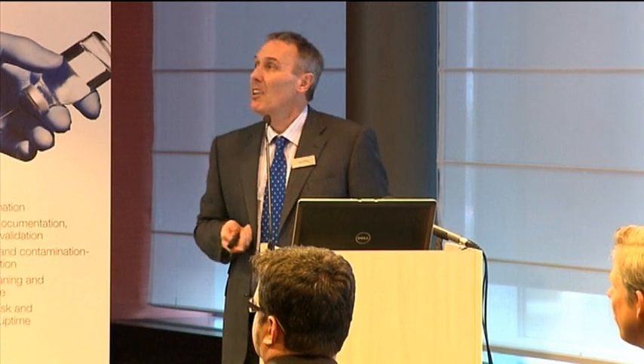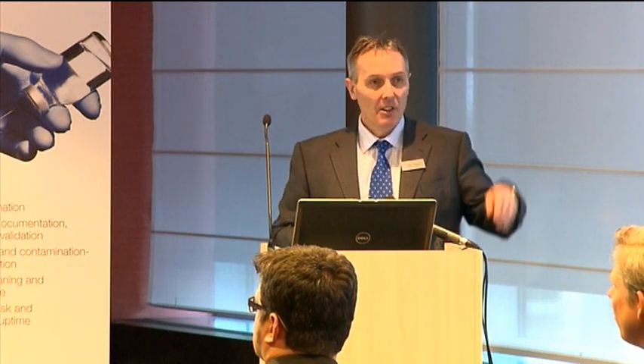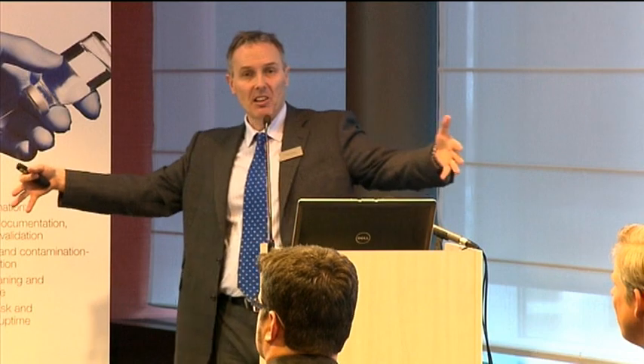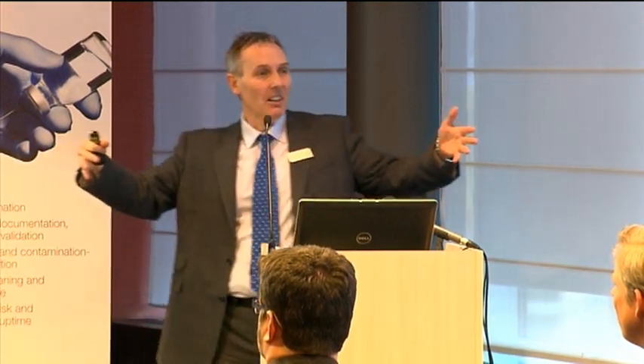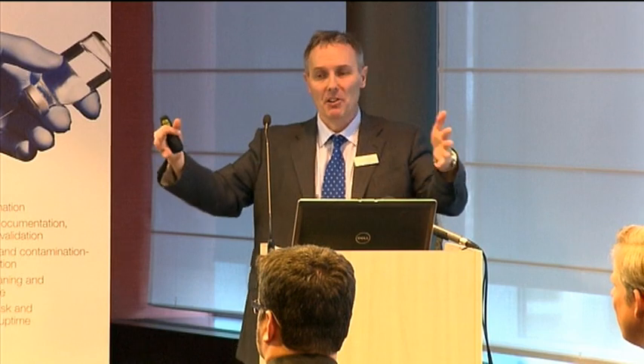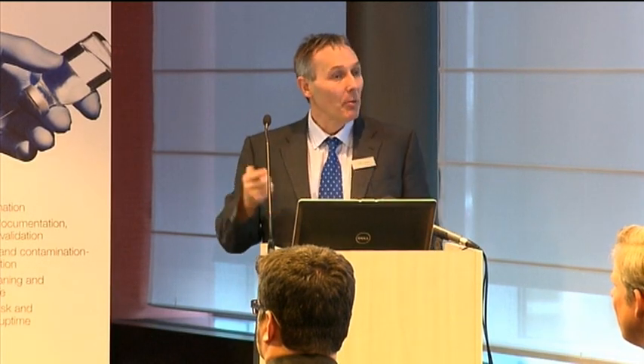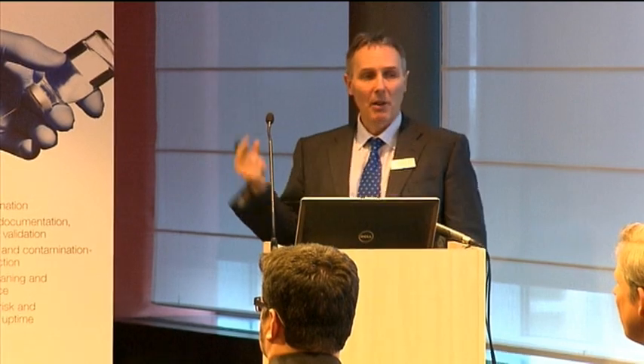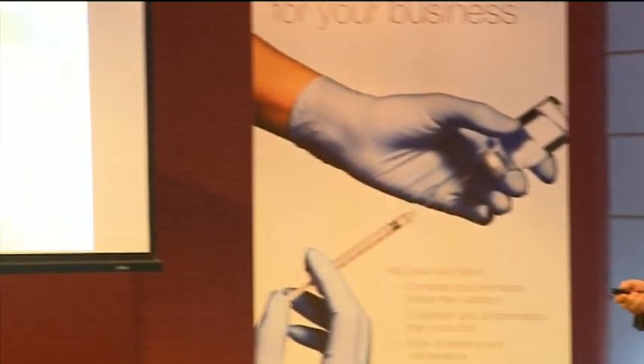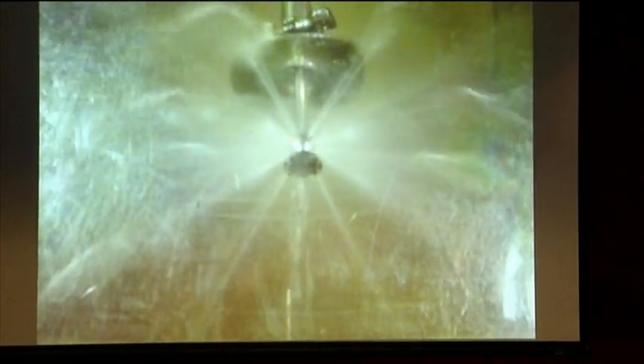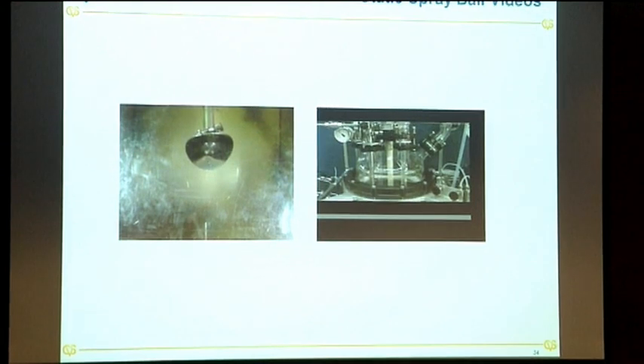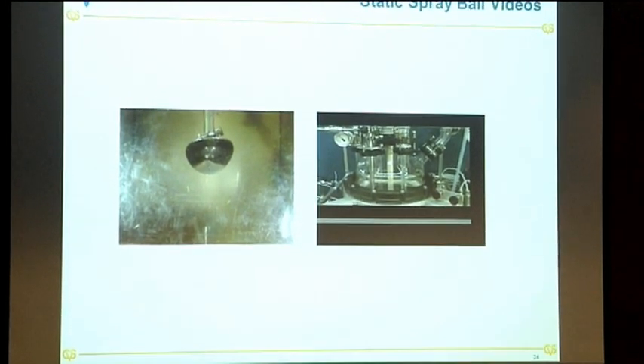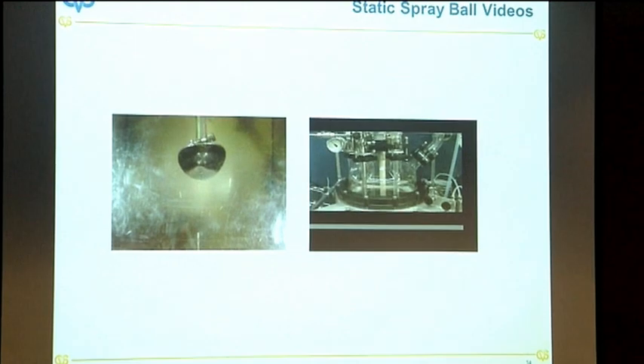So here are some spray videos. And outside there's something that looks like a big cylindrical, lovely shiny mirror polished stainless steel mechanical polish of a pop-up spray ball. So if I click this, this is a pop-up spray. The water pressure drives it down. This has got various holes around. You can spray at the sides in a fixed position. It will spray in the same place every time. And as the CIP fluid backs off, it retracts back in.